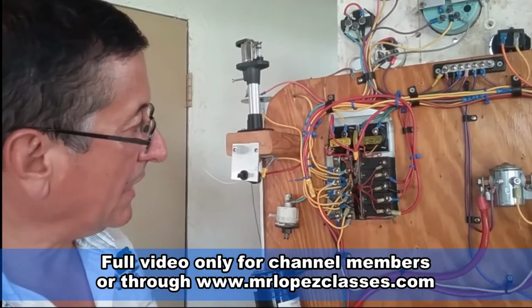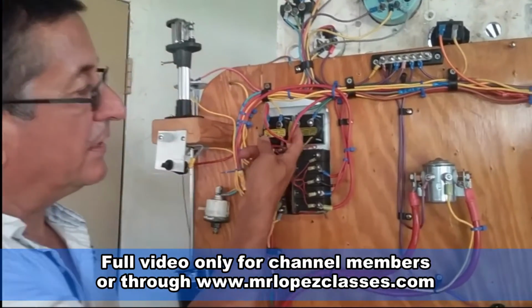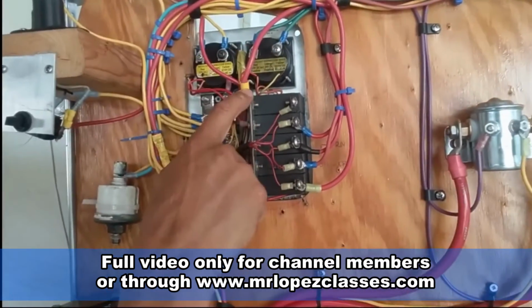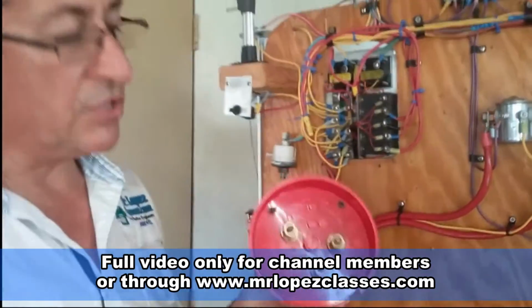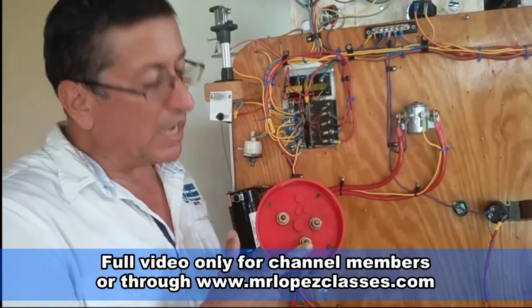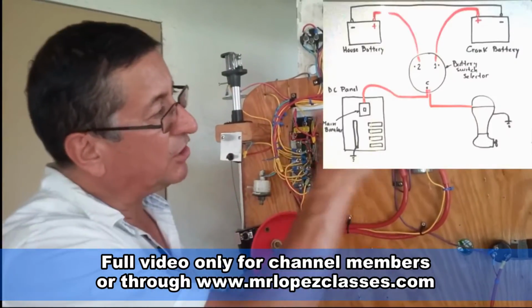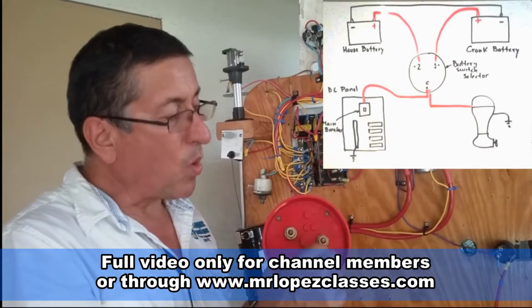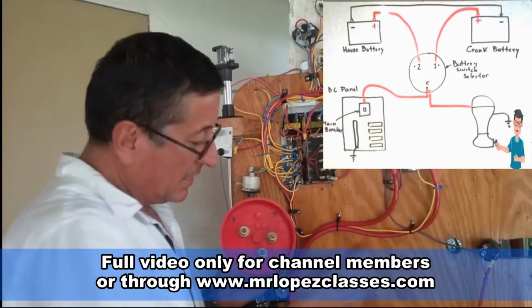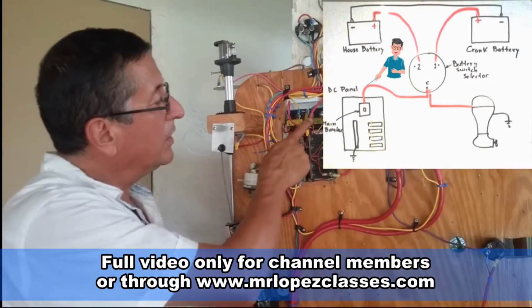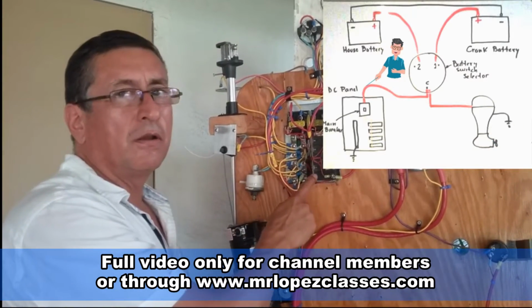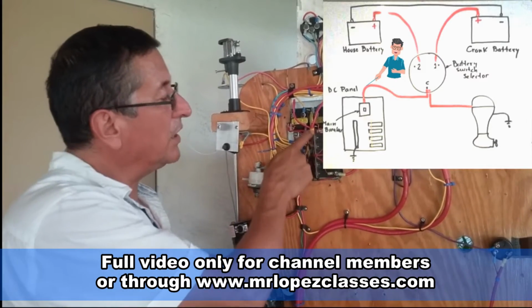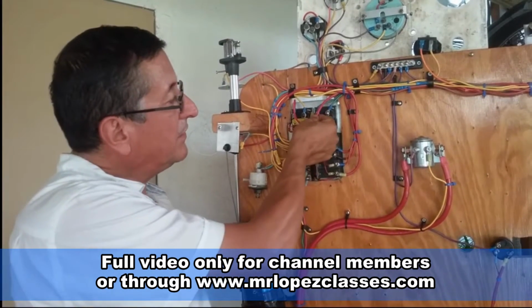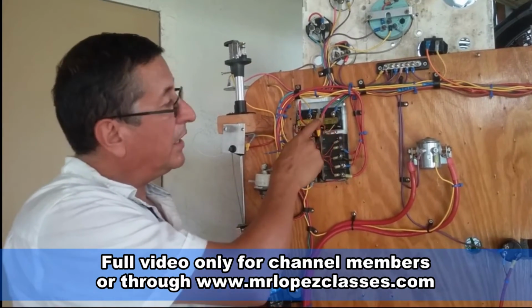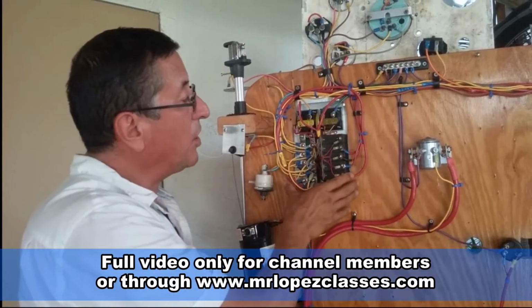All right. The first step is to calculate the gauge of the wire coming in with the power from the battery switch selector. If you remember, in the battery switch selector, you have terminal 1, terminal 2, and the common. From the common, in this particular example, you have two cables. One big cable for cranking, and another small cable in order to bring the power from the batteries into the positive bus bar.